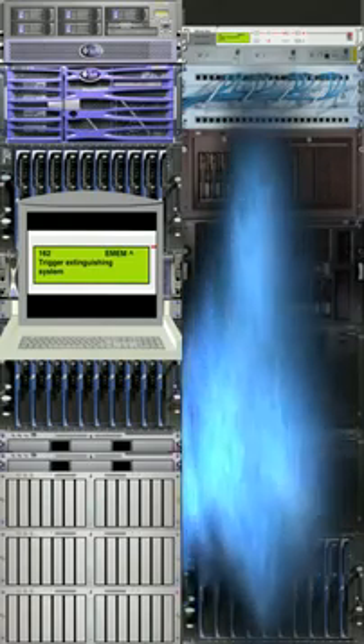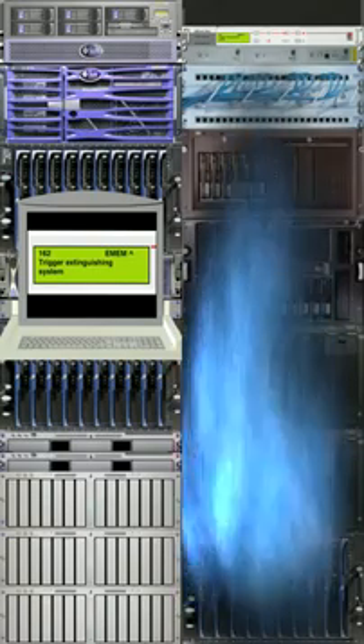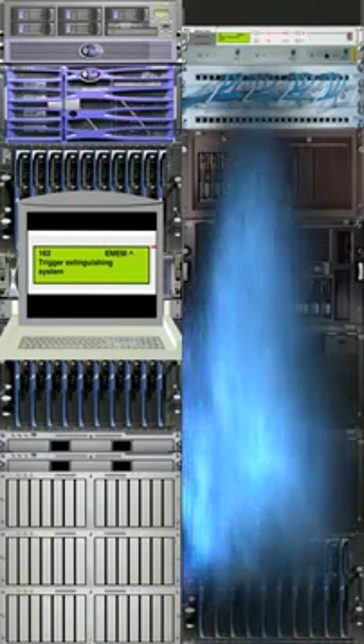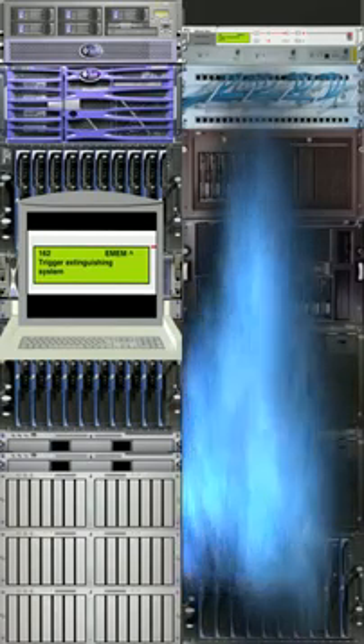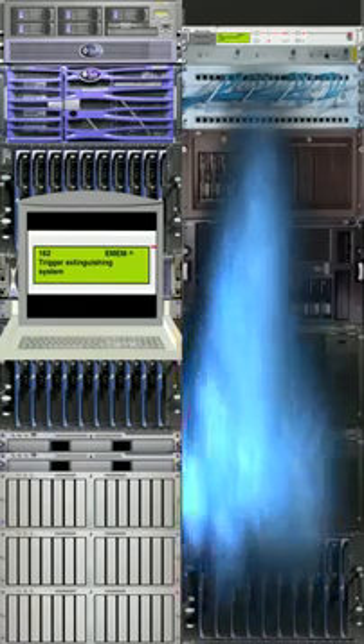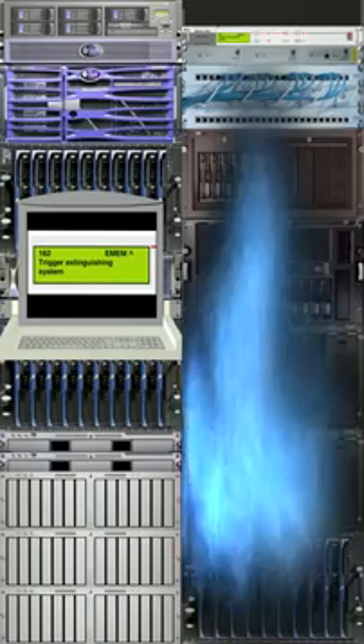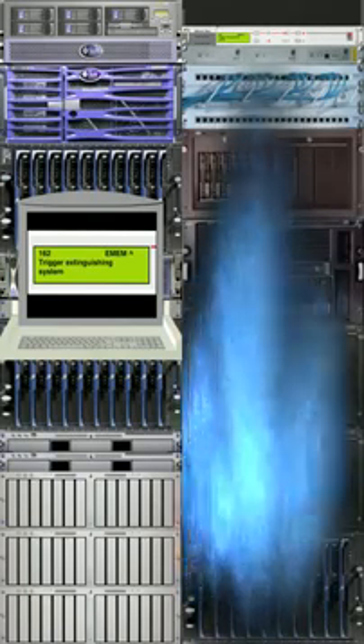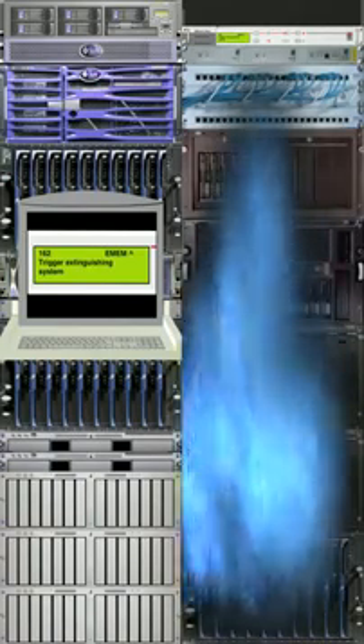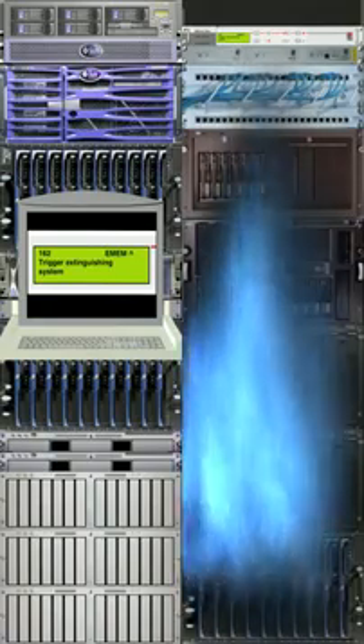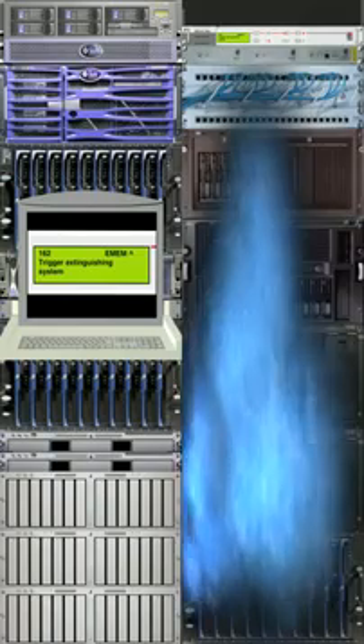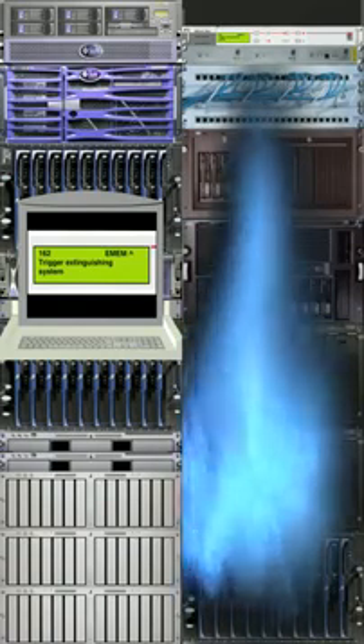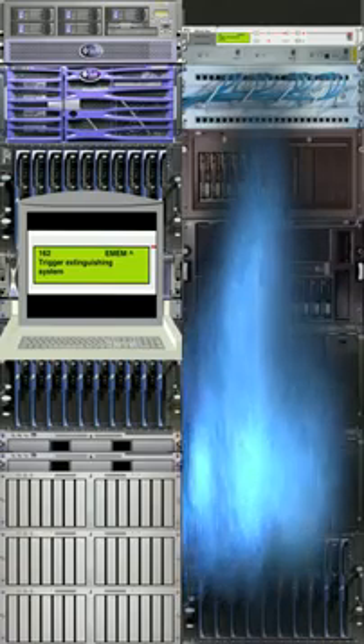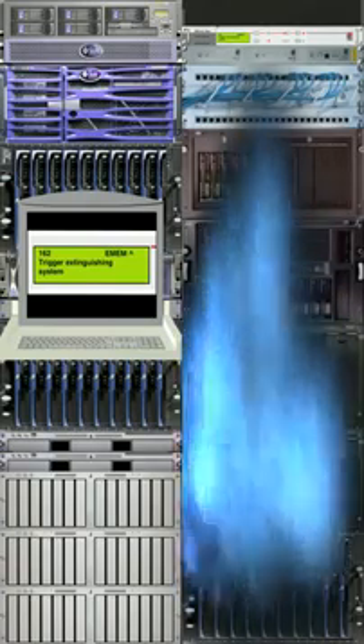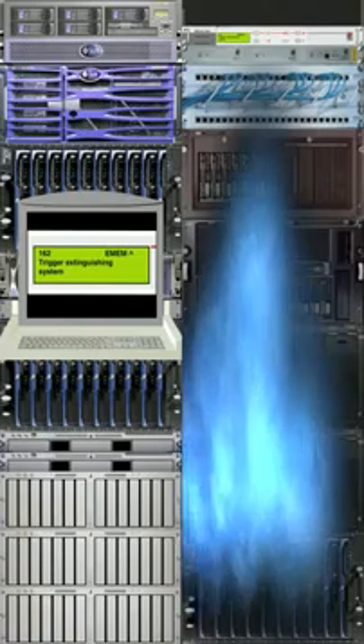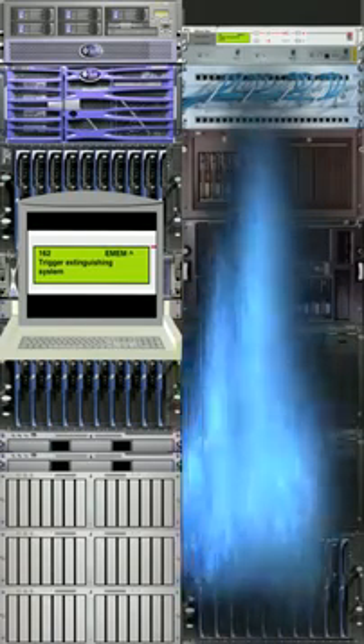The eco-friendly Novec 1230 fluid has 0 ozone depletion potential and the lowest atmospheric lifetime for halocarbon, 5 days. The closest alternative is 33 years. It has a global warming potential of 1, 99.9% lower than any halocarbon agent acceptable for use in occupied spaces. Novec 1230 fluid has the greatest margin of safety for use in occupied spaces. It makes good business sense to use Novec 1230 fluid because it's a sustainable, long-term technology.